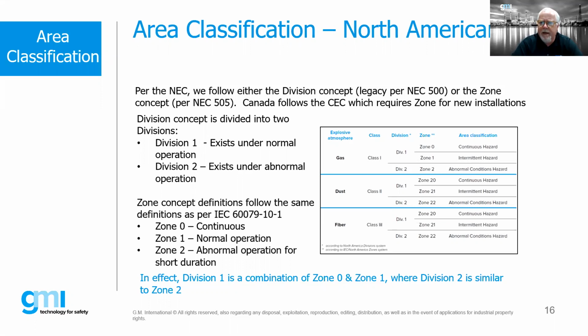Then we further subdivide under dust for Class 2 hazards, both Division 1 and Division 2. And again, those break down into either Zone 20, Zone 21, or Zone 22. And then also within the NEC, we actually have fibers and flyings as a Class 3 hazard. Again, Division 1, Division 2. In the international community, we throw those into our dust hazards as Zone 20, Zone 21, and Zone 22. So our definition, if you will, for zone applications is very similar to what the IEC follows: a continuous, normal, or abnormal operation.